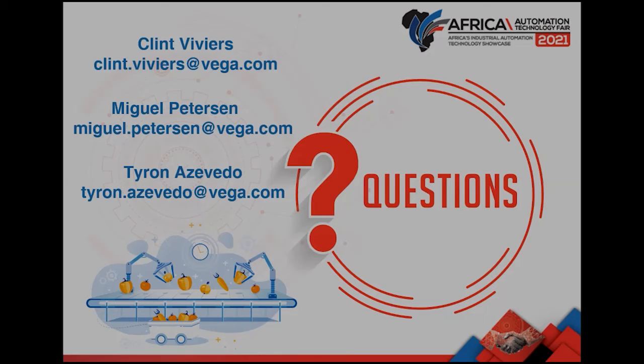And then Miguel, I'll pass this one on to you. What is the difference or advantages between ceramic and a metallic diaphragm? As Clint pointed out, the two different options within our new level devices. Thank you. The ceramic measuring cell is oil-free, a dry measuring cell, and it measures the pressure quite reliably, as does the metallic cell. But the difference is that the ceramic cell can handle rough and abrasive media and products that could have abrasive properties. The metallic cell doesn't perform too well on those because of the material. It's a very soft material, and so the robustness and the overload resistance of a ceramic measuring cell makes it a bit better in those types of applications.